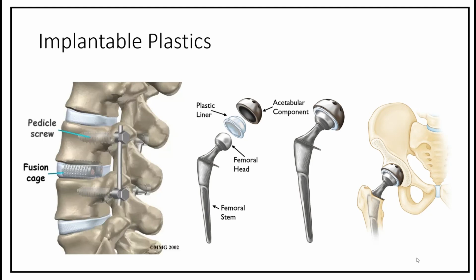development of orthopedic applications. Since implantable-grade plastics are not metallic, they do not release metal ions into the body, which can trigger allergic reactions in certain patients. Also, because they are non-metallic materials, they resist corrosion, leading to a longer implant lifespan. Another advantage is the ability to modify the characteristics of certain implantable-grade plastics. Physical characteristics such as the elastic modulus can be modified to recreate bone modulus. Mechanical properties such as the strength, wear resistance, and impact performance of polymers and composites can be comparable to metals and offer additional benefits.